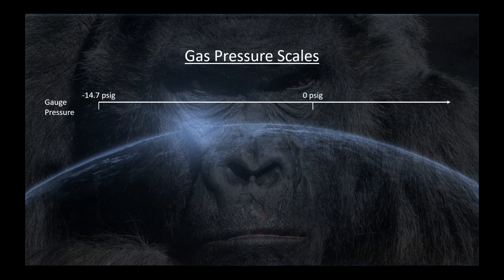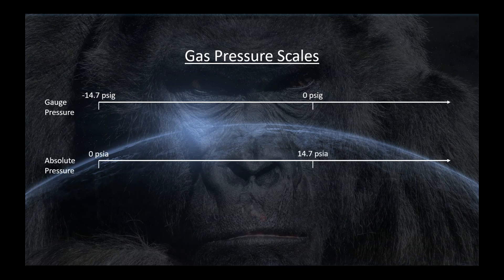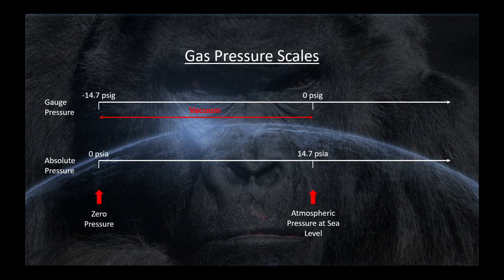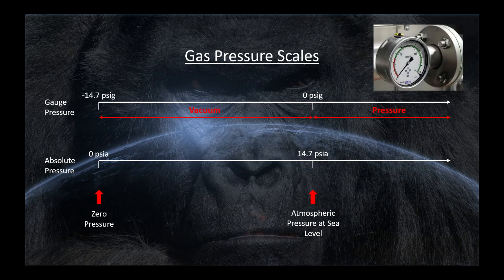Now I want to talk about pressure scales, because I think this is something that totally confuses a lot of people. We have two pressure scales: gauge pressure and absolute pressure. The difference between these two scales is the location of zero. On the absolute pressure scale, zero is literally zero absolute pressure — that point below which there is nothing; you cannot go below zero absolute. On the gauge pressure scale, zero is atmospheric pressure. A gauge pressure gauge indicates zero when not connected to anything pressurized, referenced to atmospheric pressure, so it will always show zero even as atmospheric pressure varies.